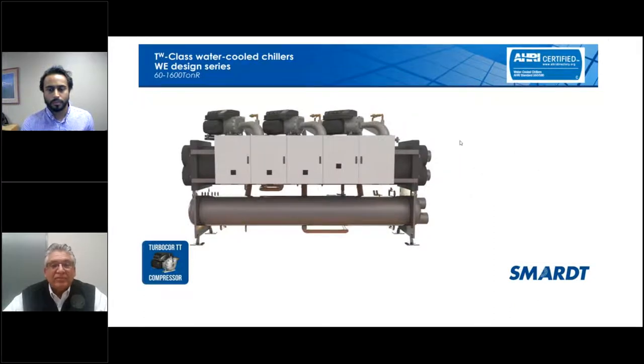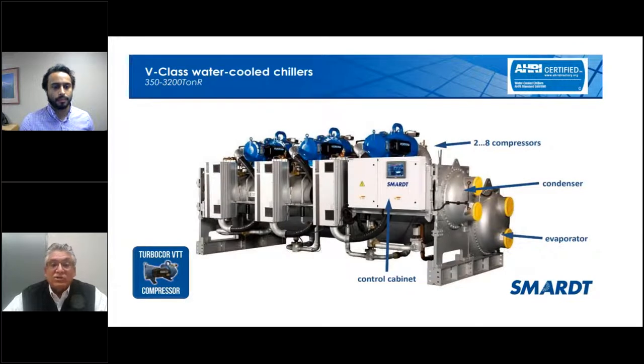Their traditional platform is vertical, like you see here, stacked on top of each other, 60 to 1600 tons. It's a great application for an area that has a small footprint and also has the ability to add additional chillers in the future. All the way up to 3200 tons, this is the more traditional approach where you have the evaporator and condenser side by side, right? In this case, we have multiple compressors mounted on top of the condenser. The suction inlet comes from the evaporator and the discharge goes straight into the condenser.